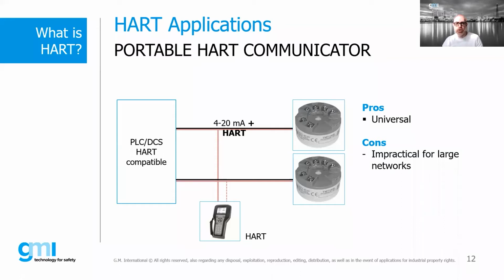Bidirectional communication with the control units makes it possible to parameterize the device without the need to be on the machine, thus being able to perform this activity even remotely. This entails a net reduction in commissioning and setup times, thus increasing business continuity. Not in all cases do traditional HART devices fully exploit their potential, but in the new generation ones, access to data is easier. This makes it possible to simplify the remote configuration, commissioning, and interrogation of the devices.